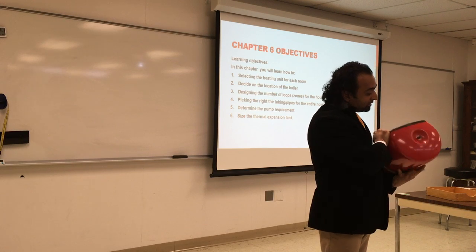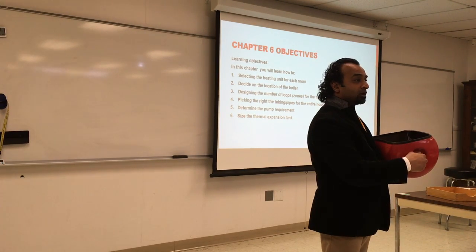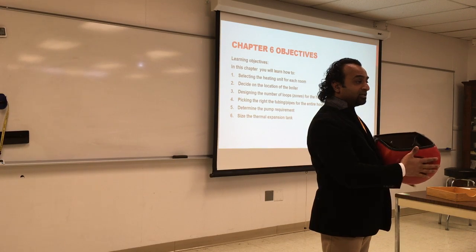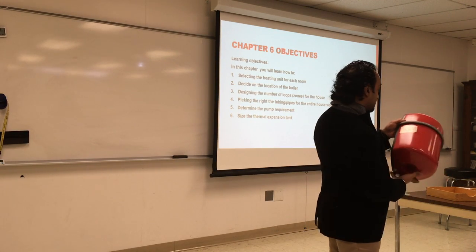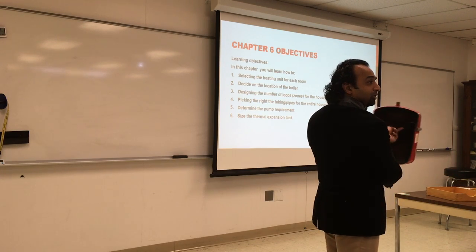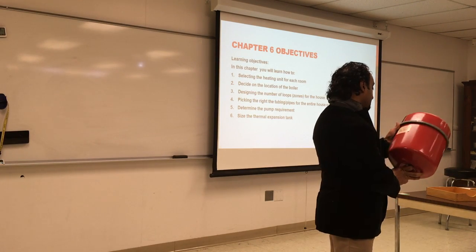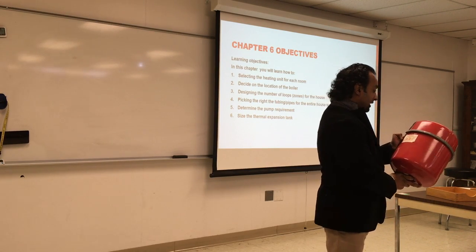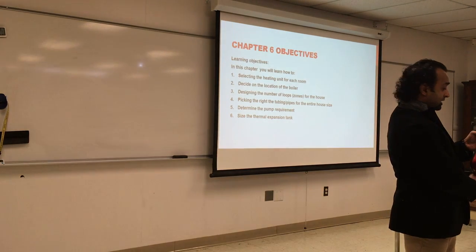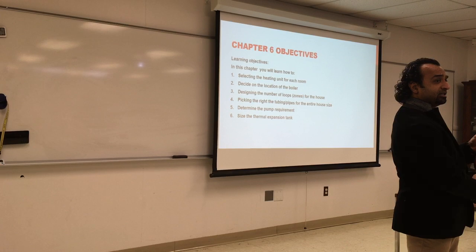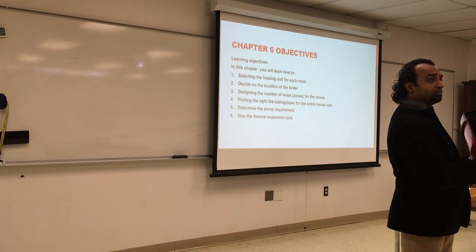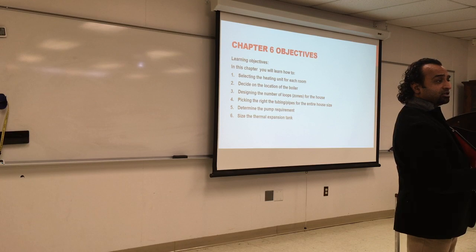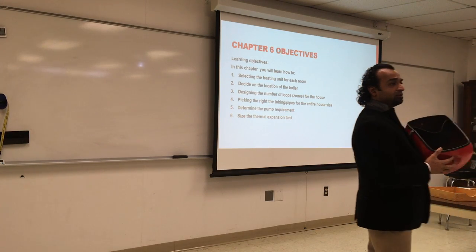And if you look here, there is a Schrader valve to keep that water under pressure. So this gets pressurized. And it has here, it's called a diaphragm expansion tank, there's a diaphragm in here to maintain it. Maximum working pressure is 60 psi, which is significant. Maximum temperature is 240. And fill pressure is 12 psi. So this one comes already pressurized, but you can go and check the pressure inside the Schrader valve. Do you use nitrogen usually? No, air. Air is just fine. Anything like an air pump? Yeah, an air pump is fine, pressurized.